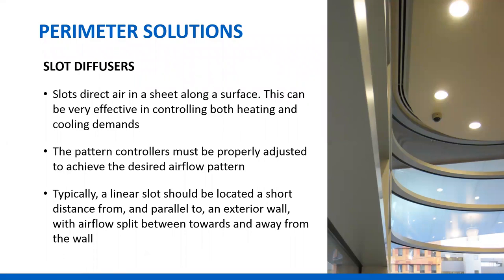The ASHRAE handbook says the linear slot should be located two feet from and parallel to the exterior wall, blowing both ways. In some cases, we see multiple slots blowing into the room and only one blowing down. In colder climates, multiple slots may blow towards or down at the window with another slot blowing into the room. Climate will determine a lot about where that happens.